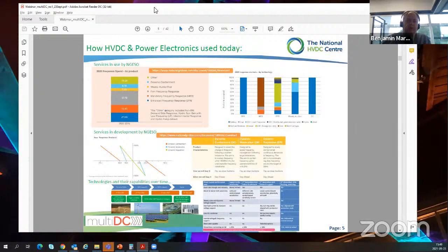So the GB system is really moving towards an emergent world where, by 2025, the expectation is that we will be managing points in time where there's close to 100% renewable technology, which will include some nuclear. So there will be some inherent inertia on the system. But when you look at a nuclear fleet, which is going to be in the region of 7 to 9 gigawatts by that stage, that's a very limited contribution towards the overall GVA second target that's required on the system. So that residual needs to be coming from other sources, be they use of synchronous condensers or use of converters providing grid forming capability, and some additional degrees of hydropower storage or spinning reserves of run of river.